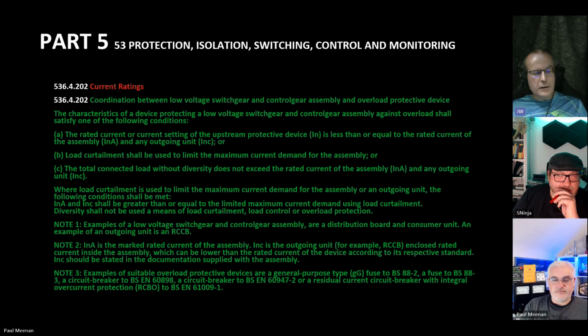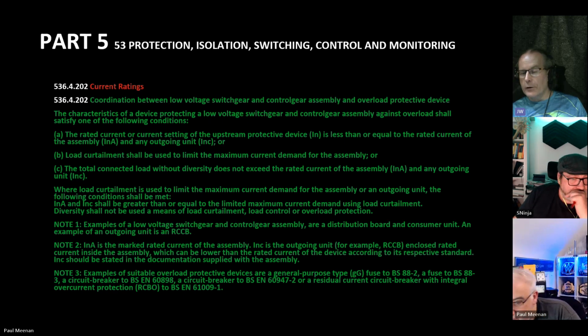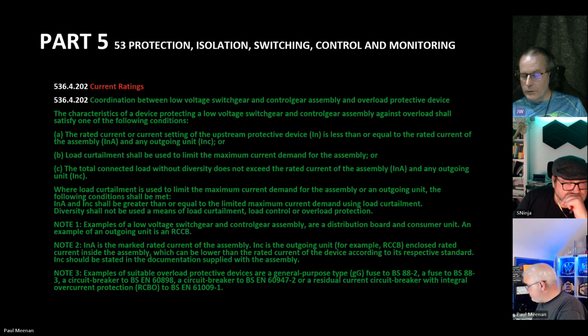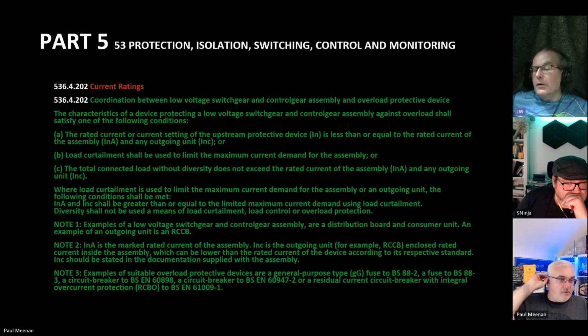So a lot of text there, but the real main points here are that in this situation you can't use diversity to reduce the total load on these devices, but you can use load curtailment, which is basically some monitoring equipment which will turn down, say, the rate of EV charging or whatever else if the current goes over a certain amount.